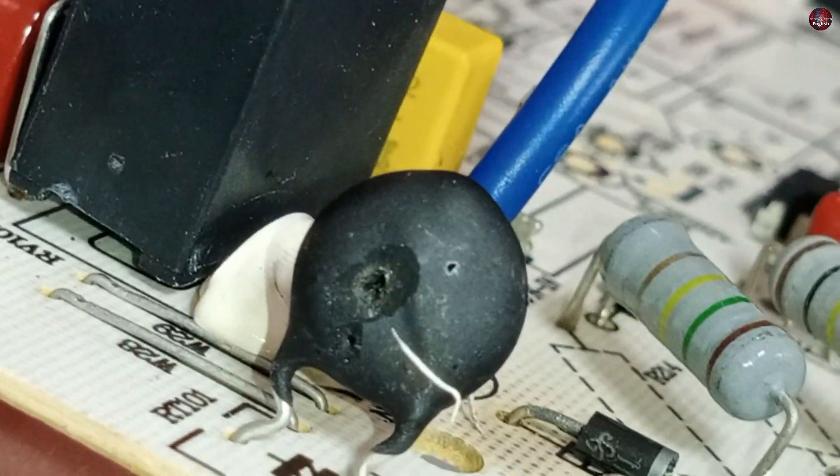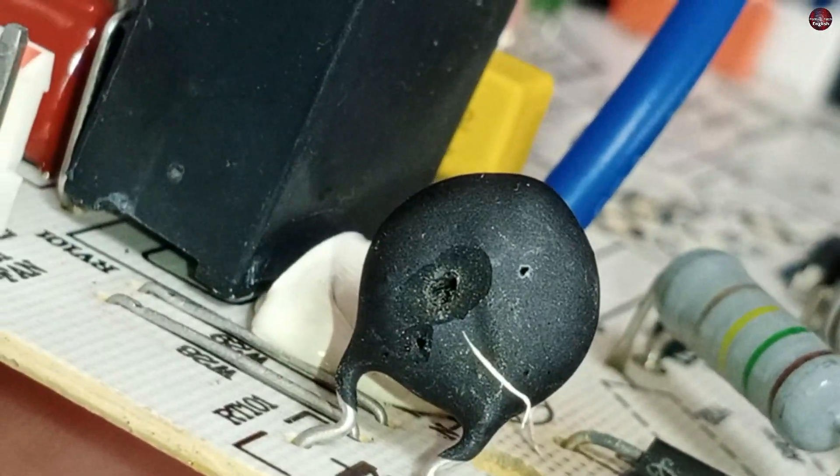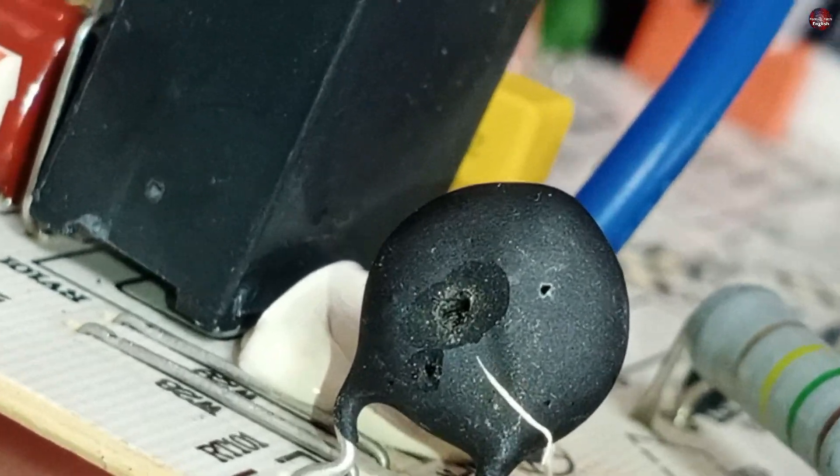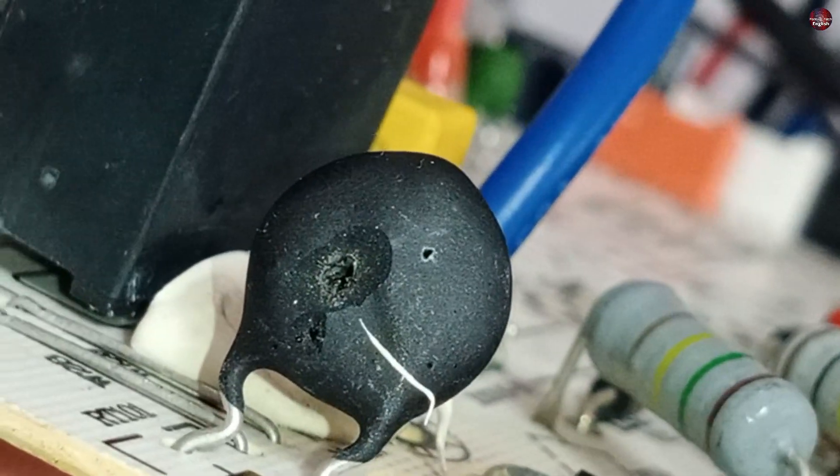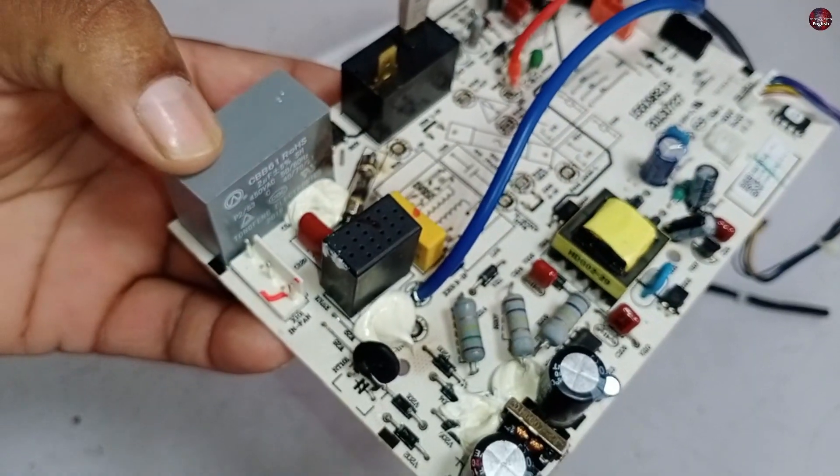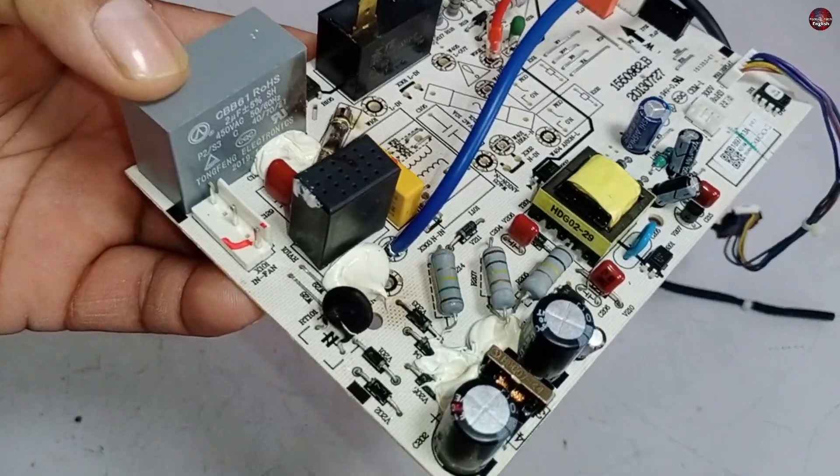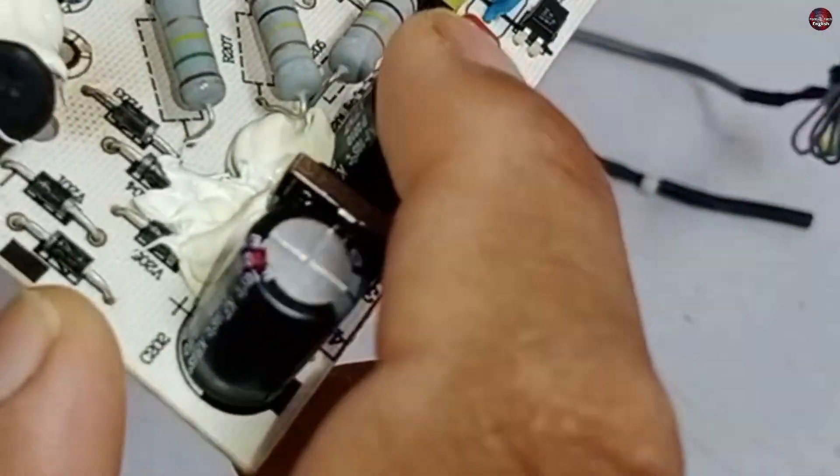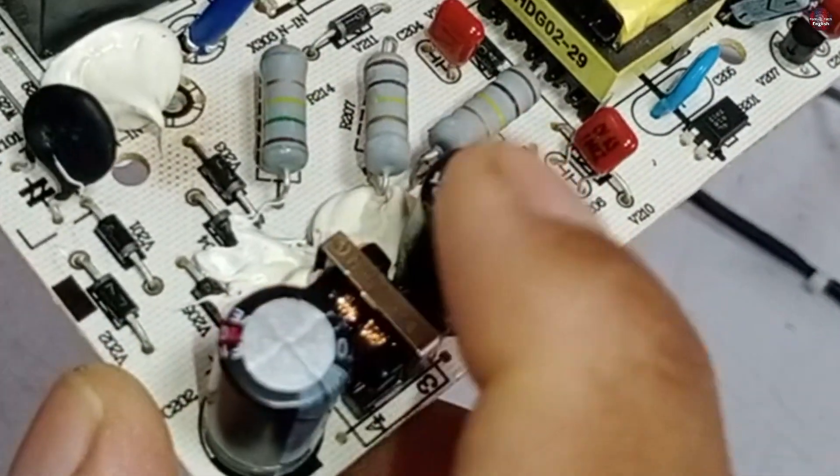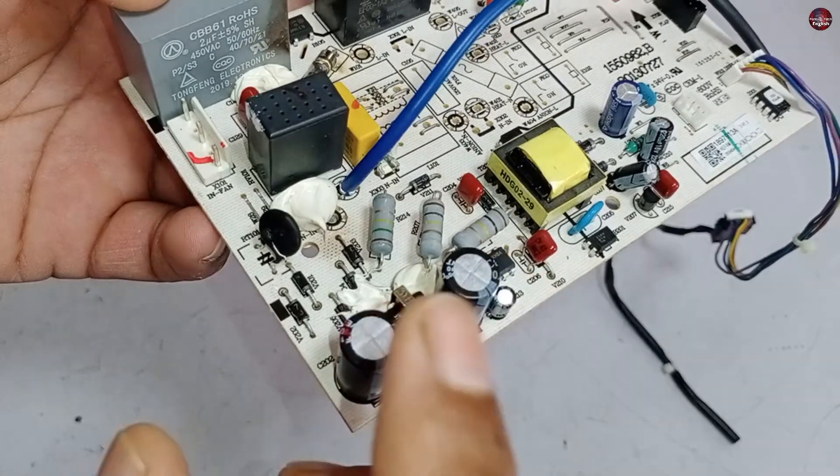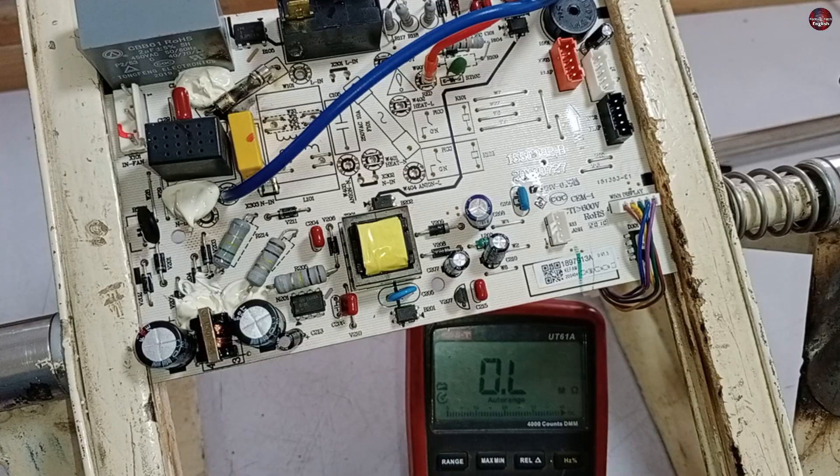This is the NTC sensor installed here. It also has a hole in it. This means this component in this circuit board is bad, and the problem could have gone further to the SMPS circuit. The good thing is that these capacitors seem okay. They are not bulged. They could also go bad. Not a big deal.